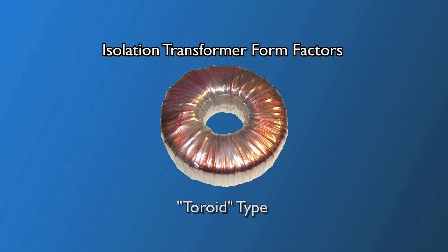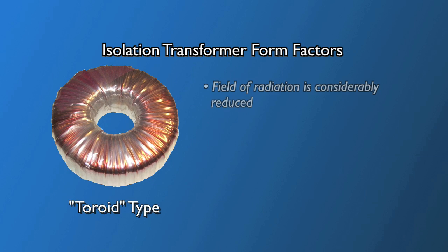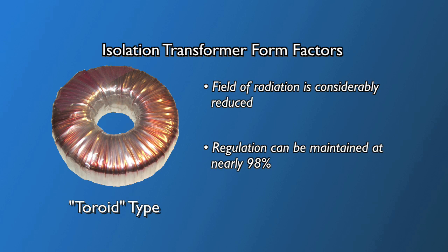Toroid, or donut-shaped, transformers have a big advantage here, as the field of radiation is considerably reduced, allowing rack mounting near sensitive equipment, for example. And regulation can be maintained at nearly 98%. This means that as current demand rises in your system, the voltage coming out of your transformer will be very close to that going in. This is simply not possible with conventional EI transformers.